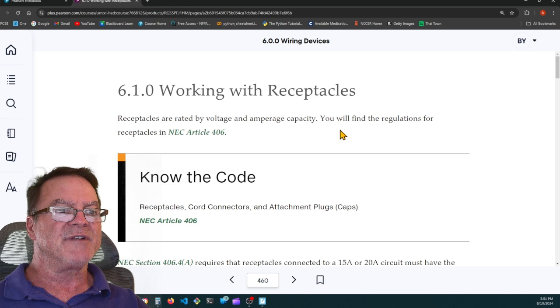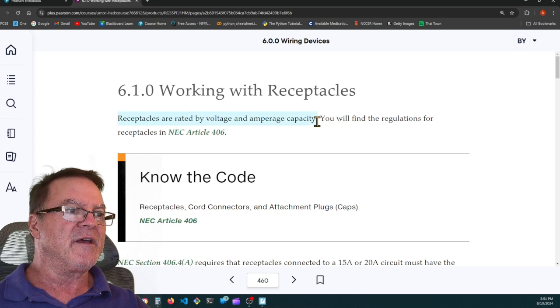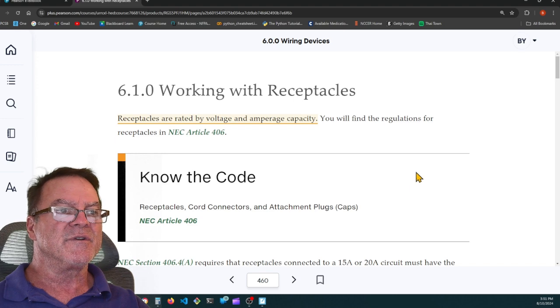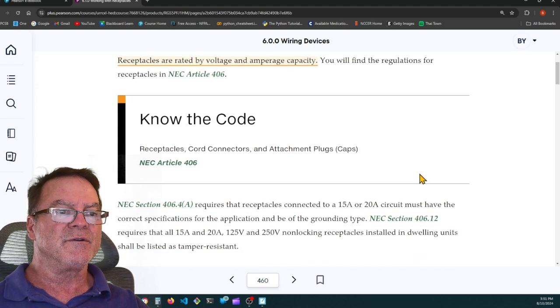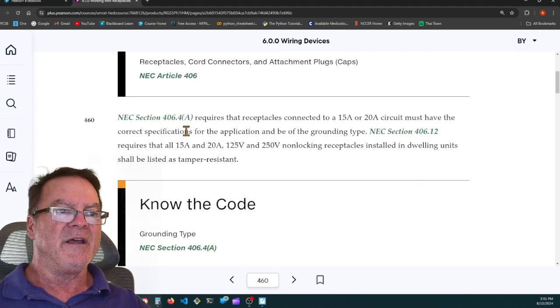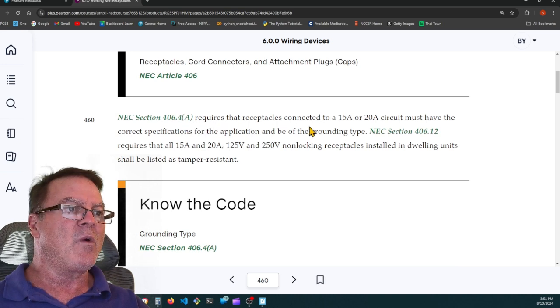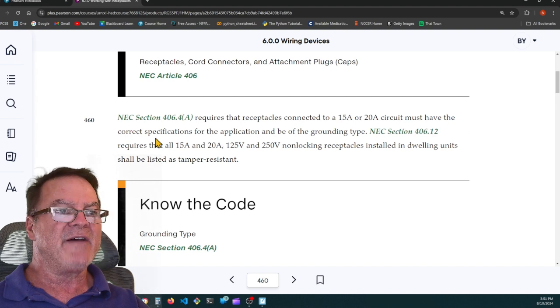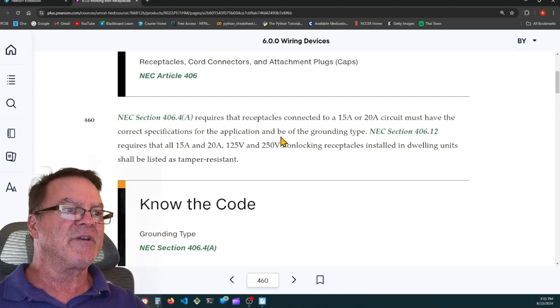6.1.0 Working with receptacles. Receptacles are rated by voltage and amperage capacity. I'm going to make that a highlight. You'll find the regulations for receptacles in NEC Article 406. NEC Section 406.4(A) requires that receptacles connected to a 15 or 20 amp circuit must have the correct specifications for the application and be of the grounding type.